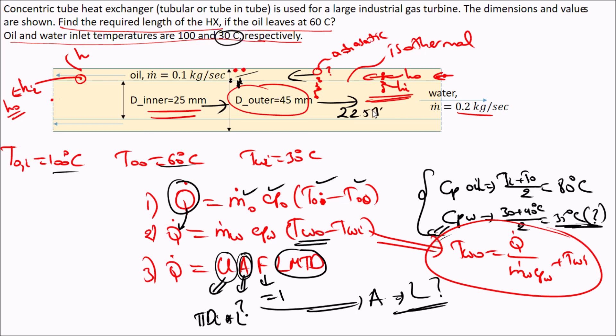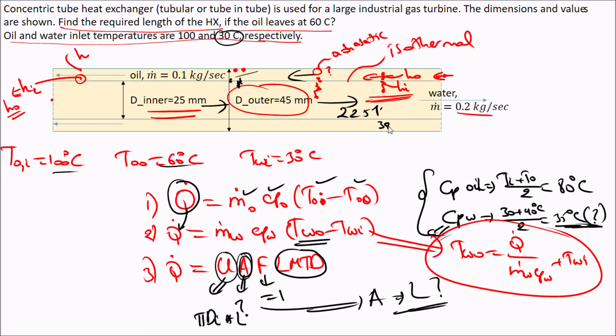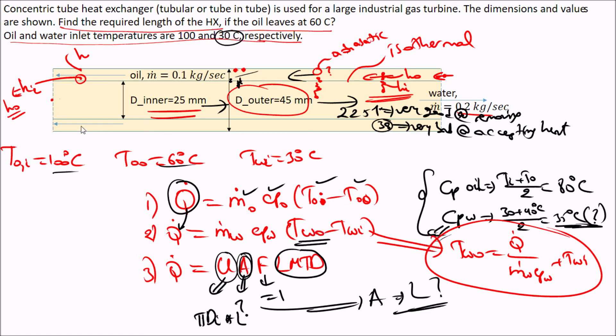Checking the isothermal wall assumption: h_inner (water side) = 2251 W/m²·K and h_outer (oil side) = 38 W/m²·K. Since the water-side h is much larger than the oil-side h, water removes heat very effectively and the pipe wall temperature remains nearly uniform. Therefore the isothermal surface assumption for the inner wall is also valid.